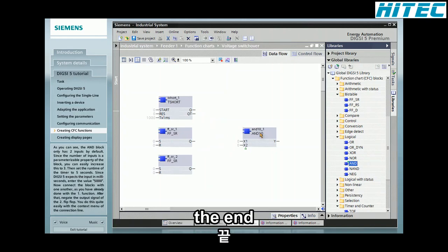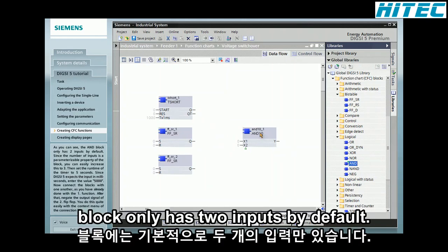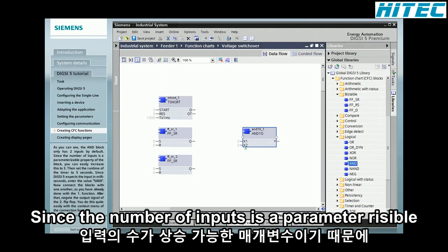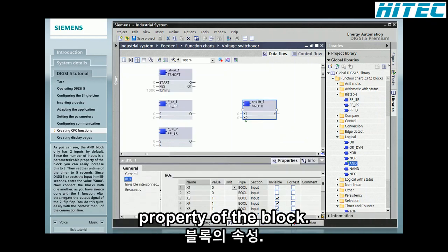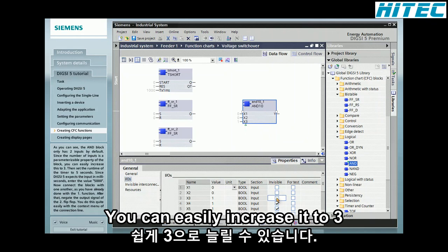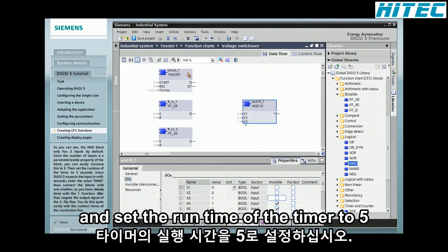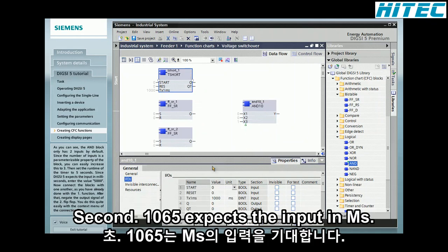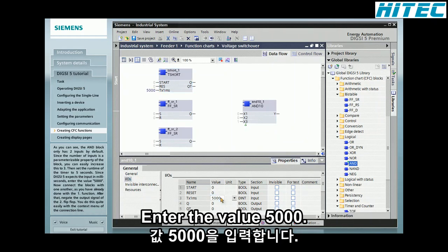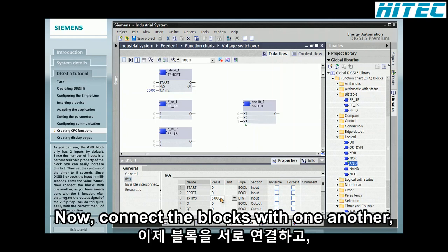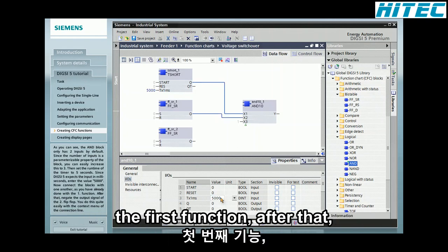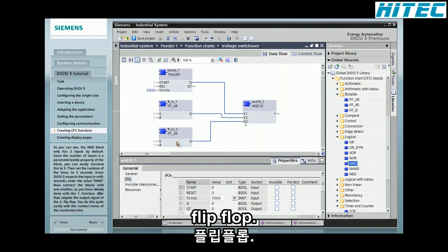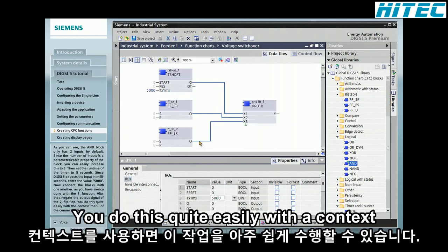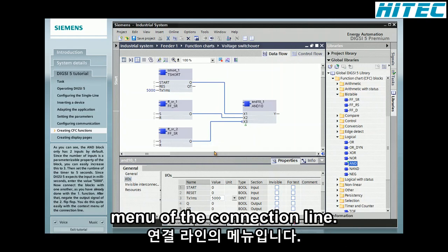As you can see, the AND block only has 2 inputs by default. Since the number of inputs is a parameterizable property of the block, you can easily increase it to 3. Then set the runtime of the timer to 5 seconds. Since DIGSI 5 expects the input in milliseconds, enter the value 5000. Now connect the blocks with one another, as you've already done with the first function. After that, negate the output signal of the second flip-flop. You do this quite easily with the context menu of the connection line.